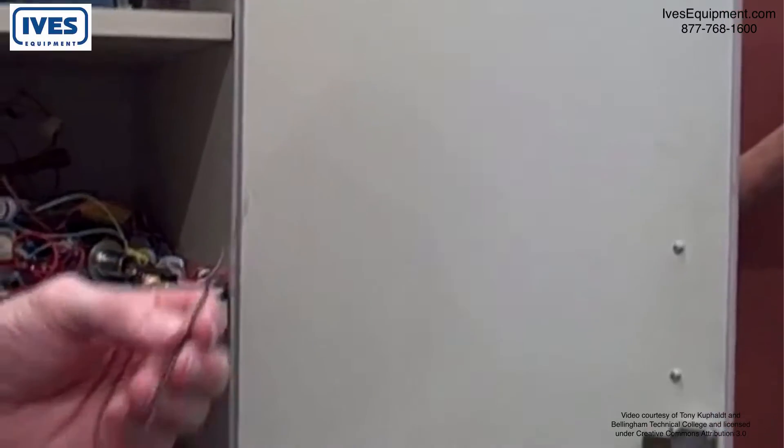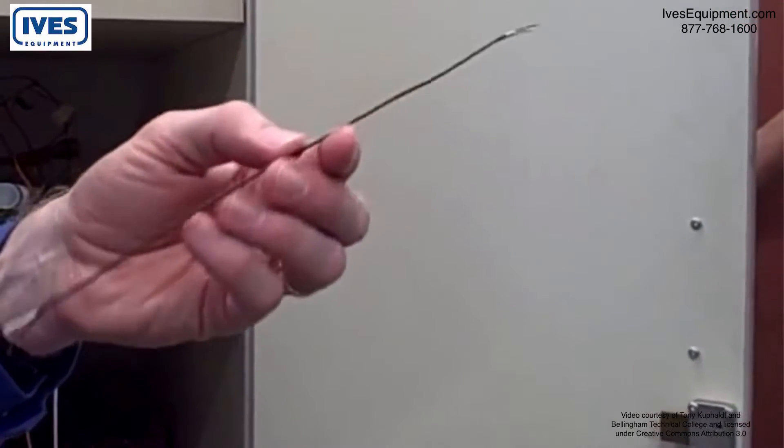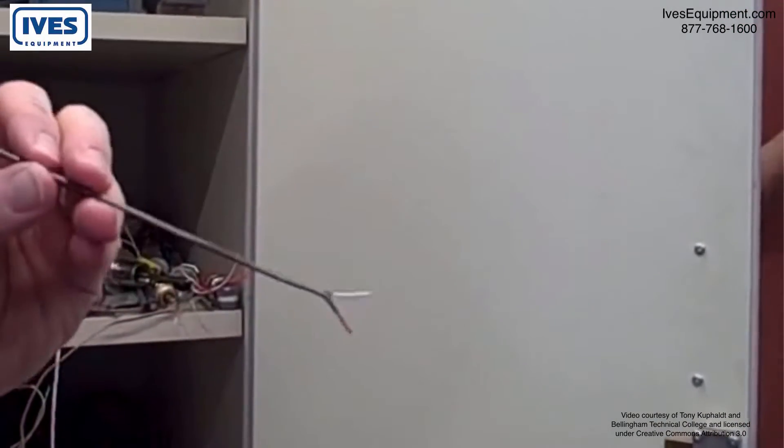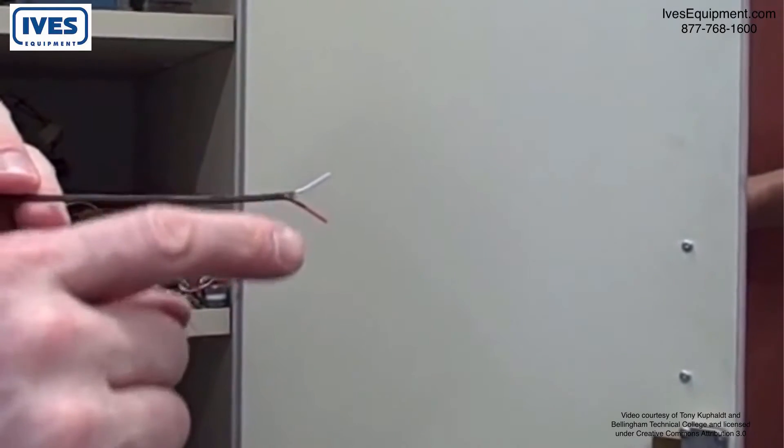Okay, what we're looking at here is a piece of thermocouple wire. This right here is type J. We can tell that from the color code, white and red, with red being negative and white being positive.